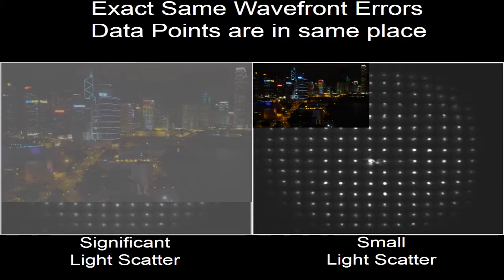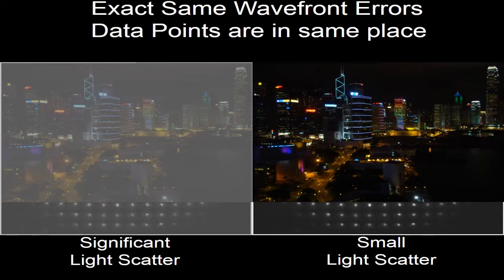Between those little dots, it should be black. If there's light scatter in the optical system from the cornea, the lens, or the vitreous, that light scatter reduces the contrast between the black background and the dots themselves. So you could actually end up with a grid exactly like the original — no wavefront distortion — but the background has a haze from light scatter. We call this signal-to-noise ratio, the contrast between the dots and the background, and it can be reduced independent of wavefront.